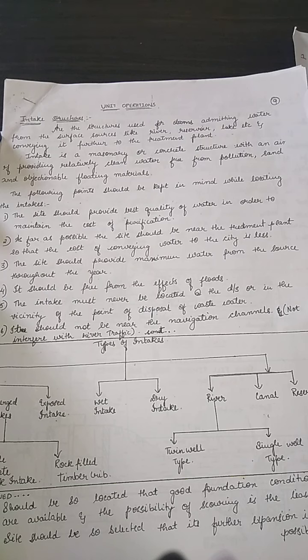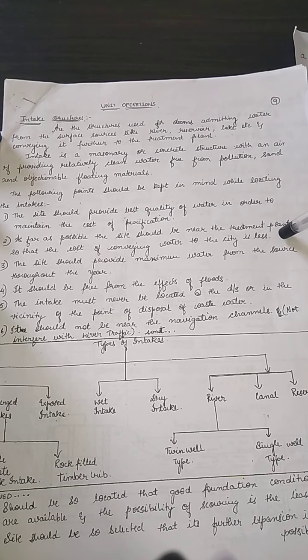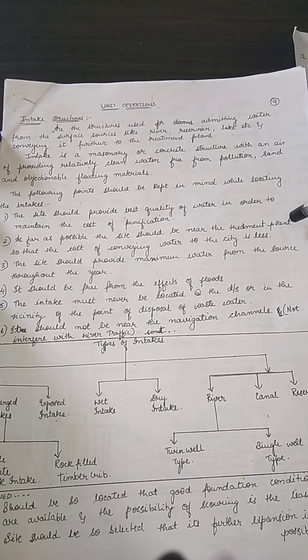Okay, then we will be seeing the site selection criteria for your intake structure. The site should provide the best quality of water in order to maintain the cost of purification. This we have talked about in detail. Then as far as possible, the site should be near the treatment plant so that the cost of conveying the water is going to be less.